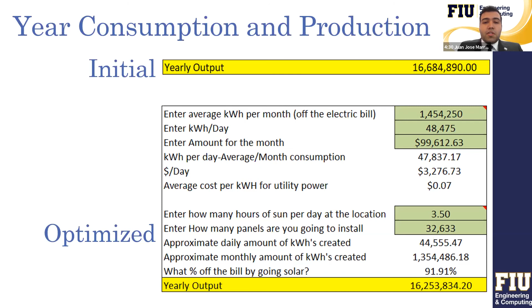Before we implemented the batteries, we tried to run REopt Lite, but when doing so, it showed us that a PV system was not required for this location due to its low utility prices, which meant that REopt could only be used for resilience purposes and to obtain the charge and discharge data based on the system design.